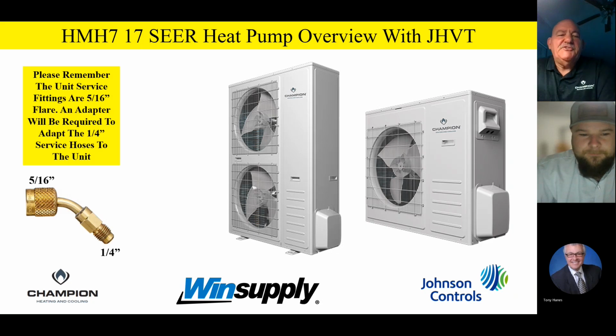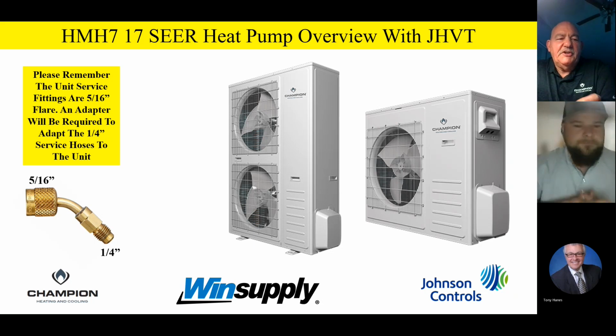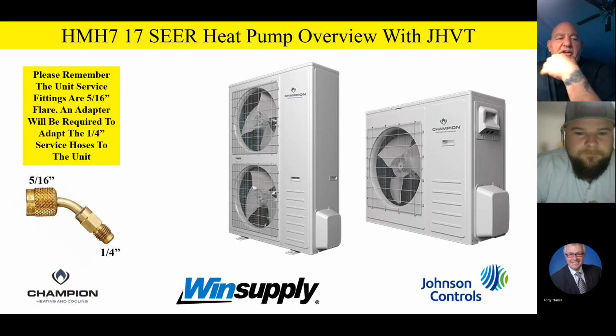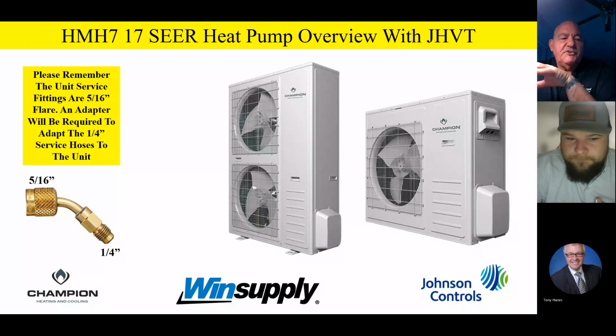We're going to go ahead and talk about the HMH7 horizontal heat pump again today. And we're going to ask that you please remember that you always have to have those special fittings that are 5/16 flare to a 1/4-inch flare. What that does is it allows you to hook your service hoses up to these things. Now, Daniel, I don't know if you guys carry those at your location, but it's something you definitely want to consider having some of those, because for the guys to get their service hoses on those, they're going to need those. And so make sure you mention that during the training or whenever you have opportunity to talk about the unit, make sure you've got some of those fittings.